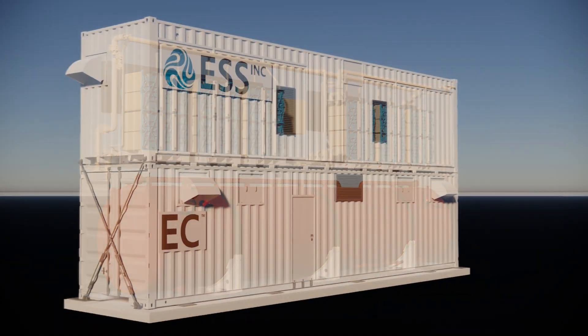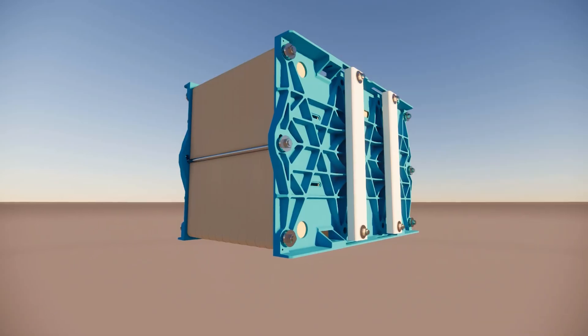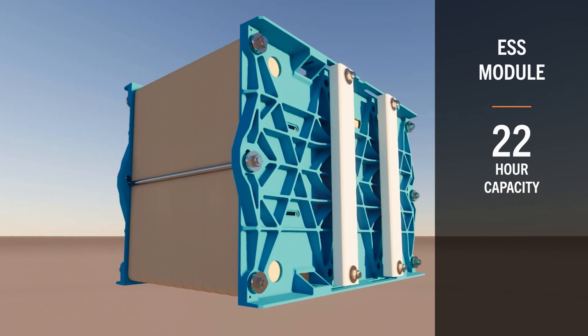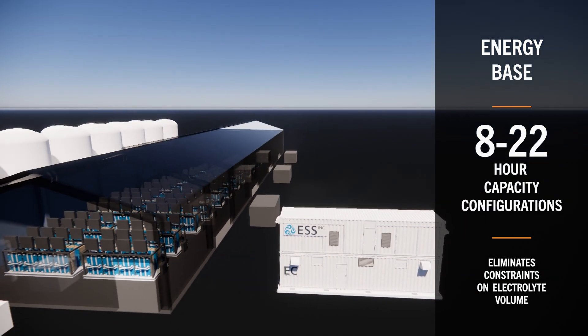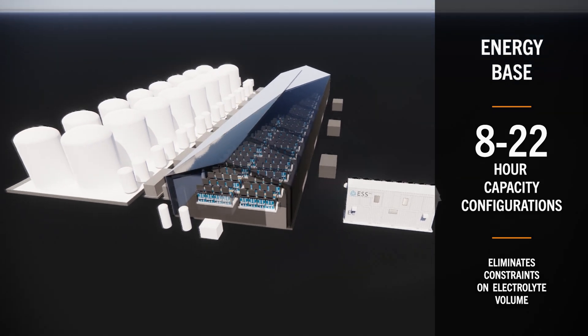Historically, ESS system capacities have been constrained by shipping container volume, limiting capacity of an energy center product to about 8 hours. The ESS battery module is intrinsically capable of plating enough iron to hold up to 22 hours of energy. The new Energy Base product line is able to decouple power and energy by eliminating constraints on electrolyte volume.